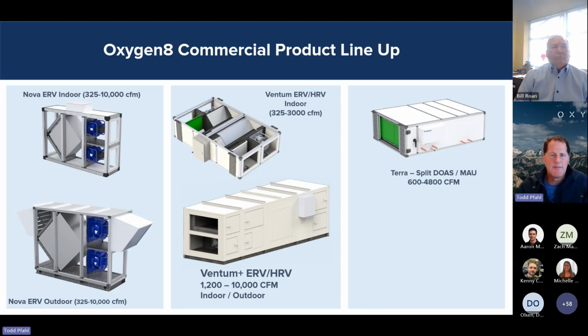At Oxygen8, we have a lot of different solutions. Out there on the left is the cross-flow core. These cores have been around for decades now. Basically, you have airflows that are parallel in the same direction that cross as they go through the core. This gets you your standard ASHRAE 90.1, 50 to 55% total energy recovery. In the middle, we have a newer design called a counterflow core. We're starting to see this more in North America, where we have parallel airstreams, but they are opposite in direction. So I have a large delta T across the heat exchanger, and that gets me energy efficiencies of 70 to 75% total energy.